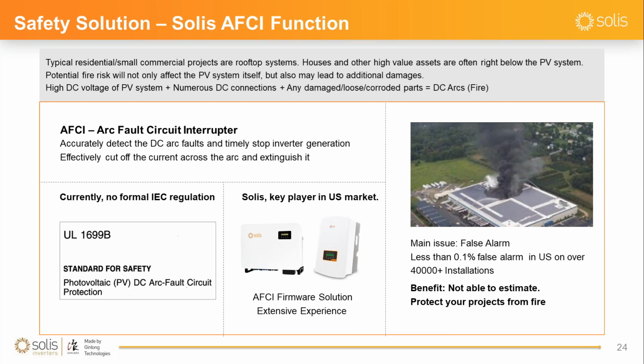And in that way, we can solve the false alarm issue and keep the false alarm rate at a very low percent, because one key problem of AFCI detection is that if you detect the arc falsely, then the inverter must be shut down, and the inverter shutdown will cause a reduction of your generation. So our solution has a quite low false alarm rate, and keeps the system working without affecting the generation of your system much. So this is the AFCI protection that we're going to have on our inverters.